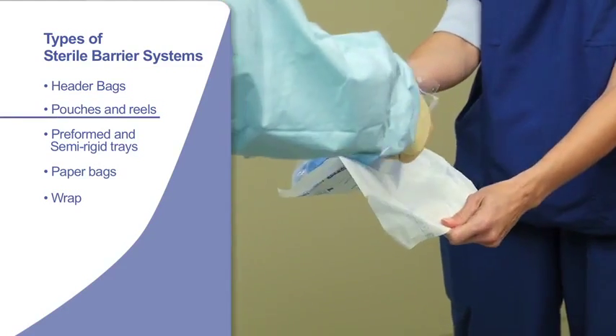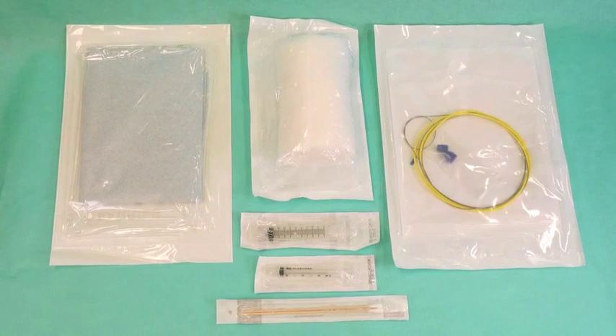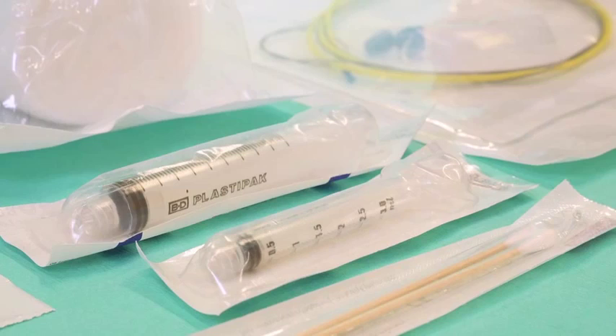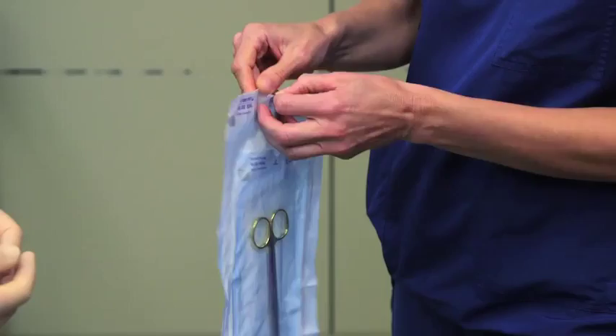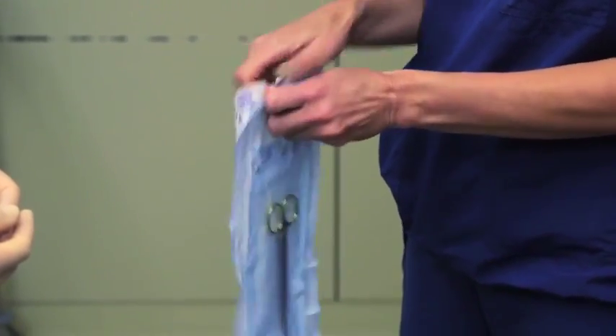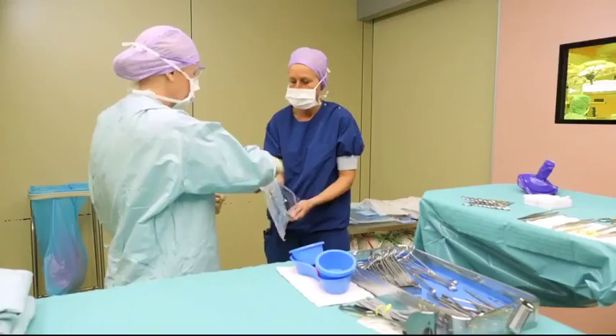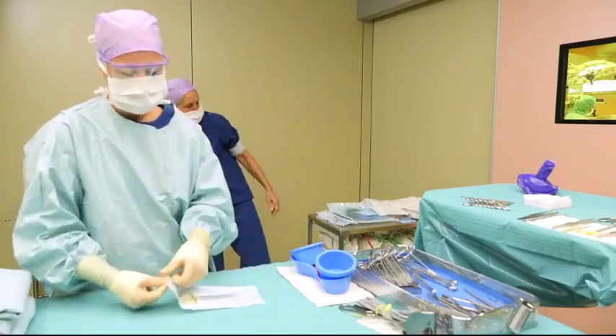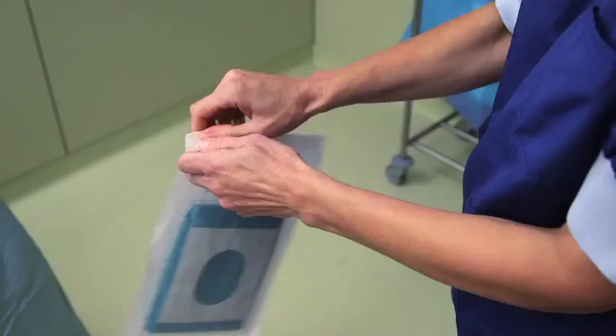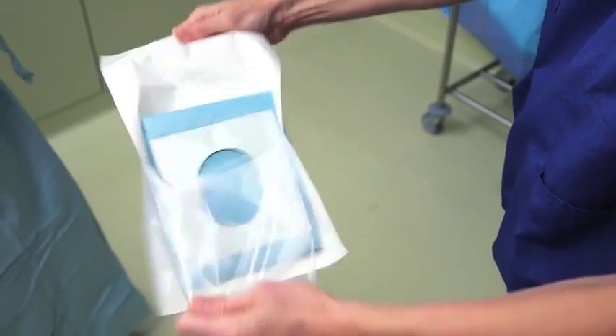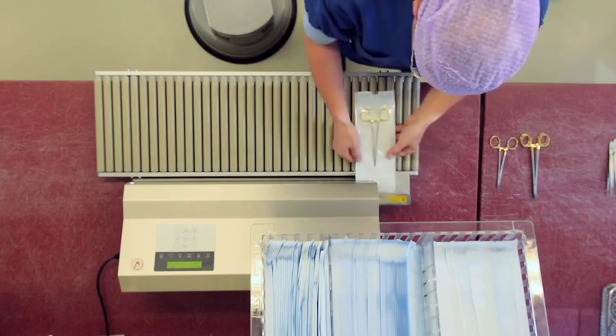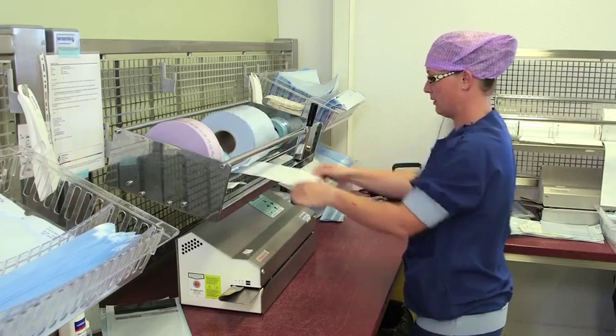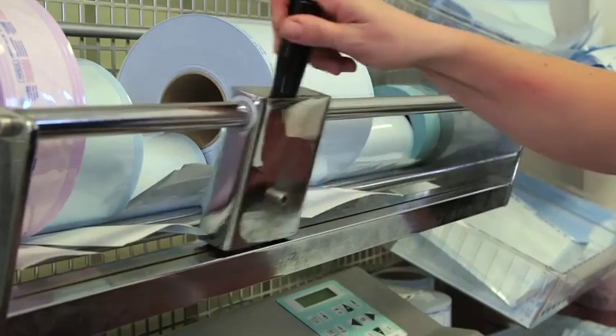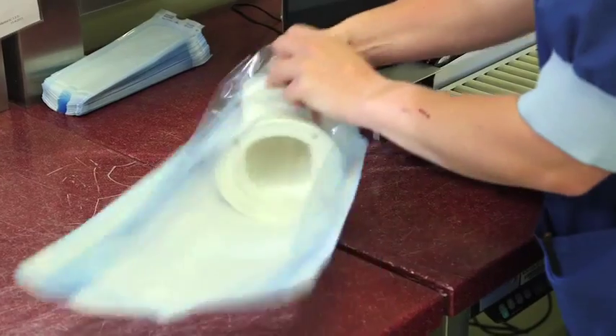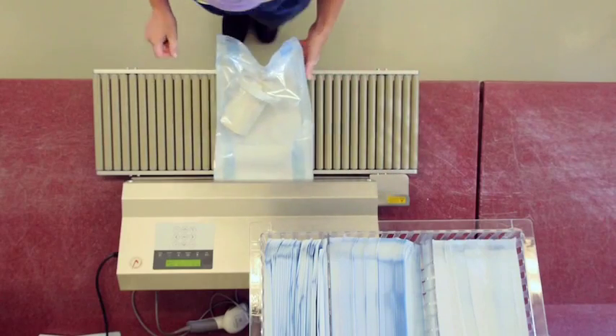Pouches and reels are made from plastic film and a permeable microbial barrier material, which is typically a medical-grade paper or a spun-bonded polyolefin non-woven, which allows access to the sterilizing agent. Pouches are commonly used as packaging for single instruments, small sets of instruments, and single-use medical products. Pouches are also available pre-formed or in a reel, which allows individual cutting to length. Products with gusseted film allow for larger volumes.